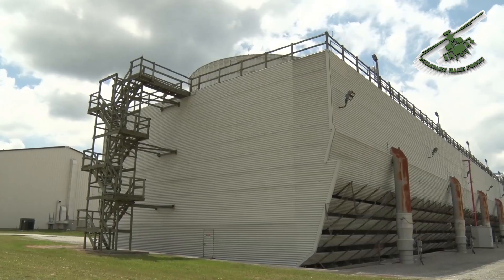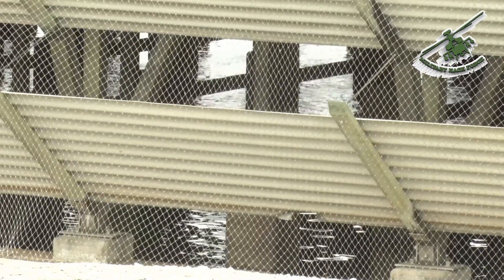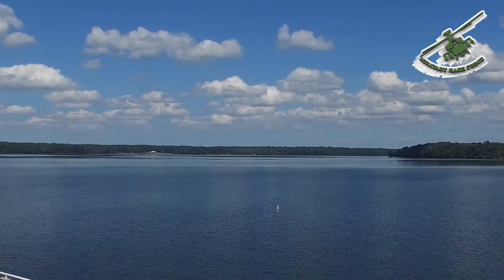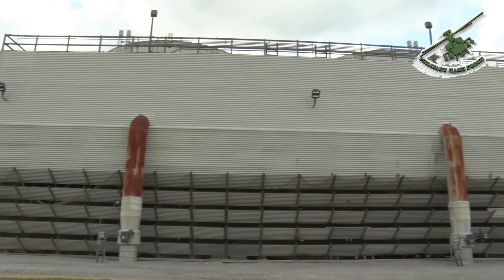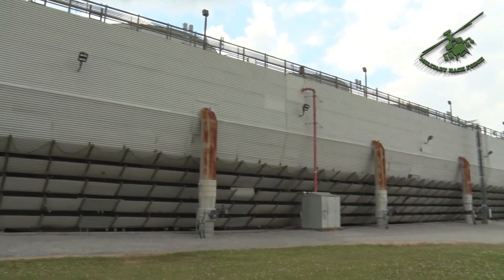With exhaust reaching up to 3,000 degrees Fahrenheit, heat exchangers and tremendous amounts of water are needed to cool it down to protect the exhaust compressors. The water sprays require up to 200,000 gallons of water per minute, pumped in from a nearby reservoir.